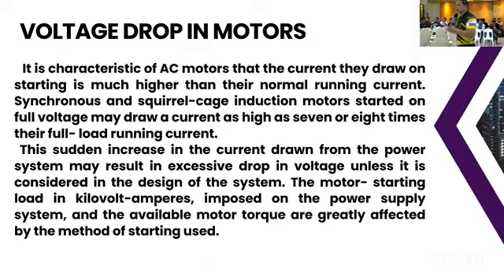Okay, we have also voltage drop in motors. A characteristic of AC motors is that the current they draw on starting is much higher than their normal running current. Synchronous and squirrel cage induction motors started on full voltage may draw a current as high as 7 or 8 times their full load running current. The sudden increase in the current drawn from the power system may result in excessive drop in the voltage unless it is considered in the design of the system.